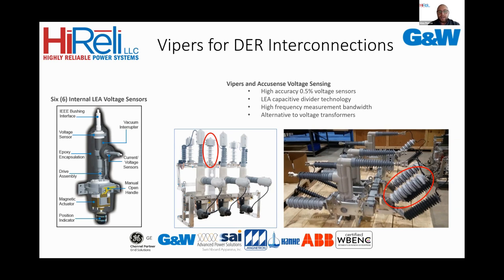voltage sensors. So as we move forward with the standards, there's the IEEE 1547/2018 standard that gets into the DER interconnections, and there's more requirements on islanding and syncing the DER with the grid, as well as your different ride-through requirements. So G&W has their AccuSense voltage sensors, which are circled in the red. The one in the middle is a 15 or 27 kV sensor. The one on the right is a 38 kV sensor. So you basically have two sensors that cover you all the way up to 38 kV. Same capacitive technology, and these actually are 0.5% accurate.